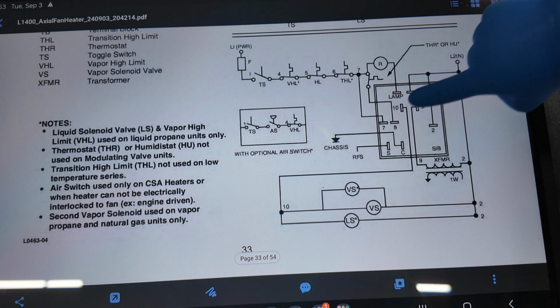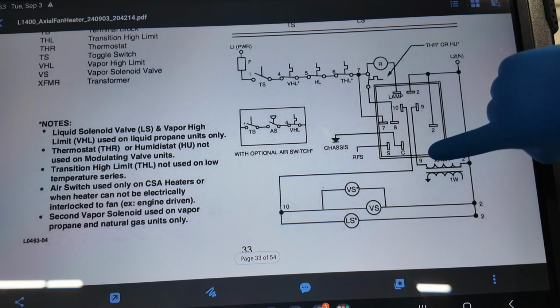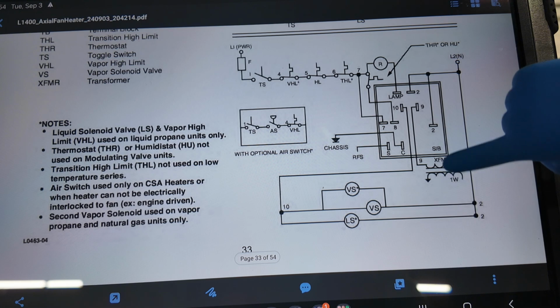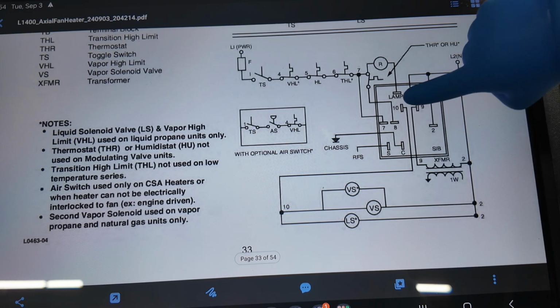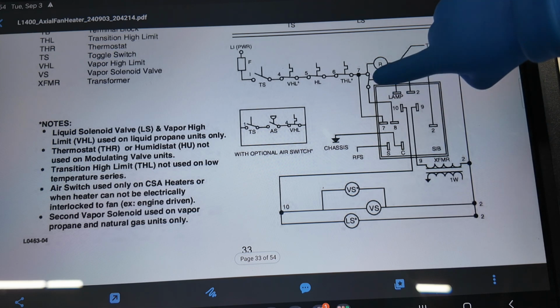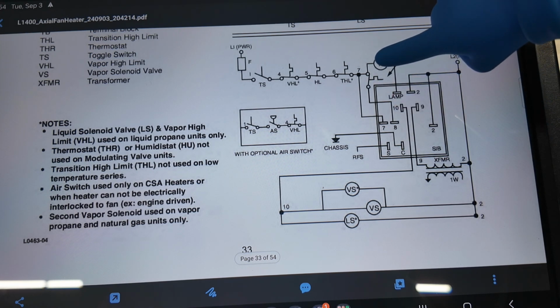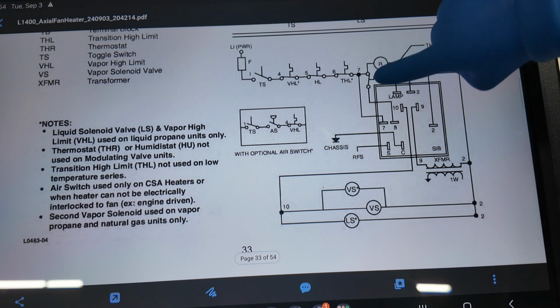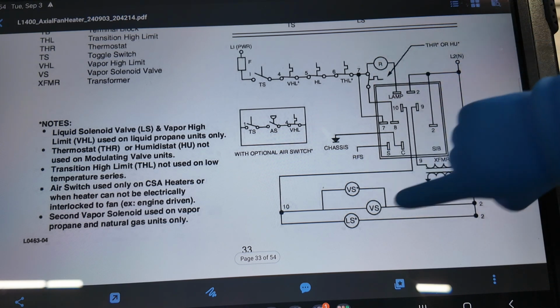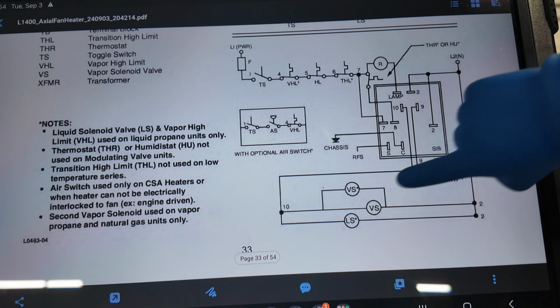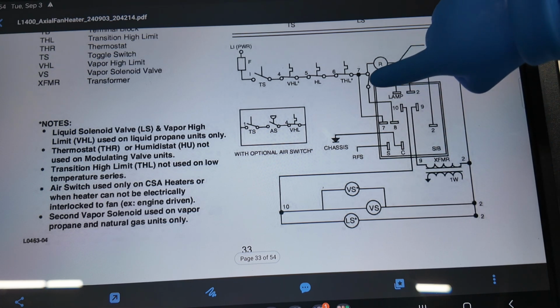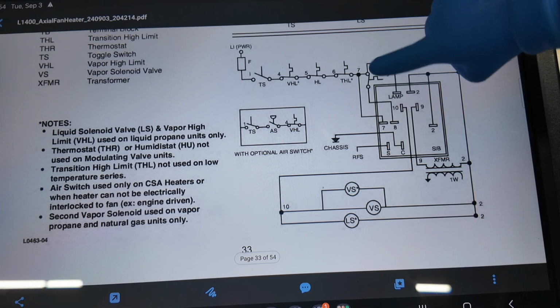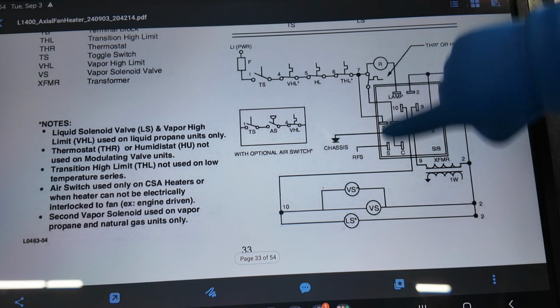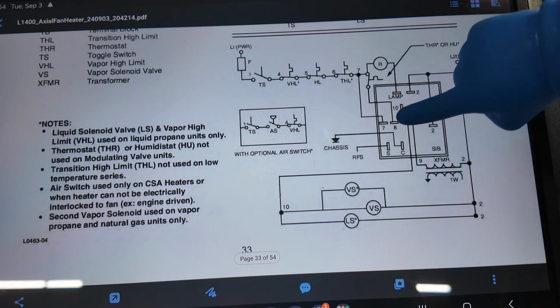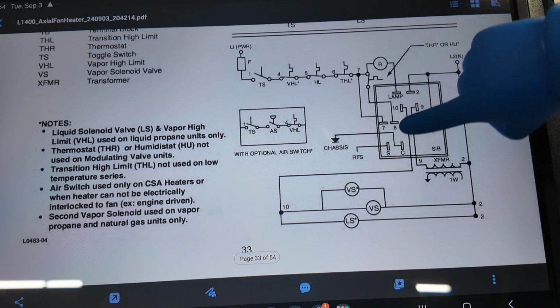You will get power on 9 and 10. 9 will have power for a short time to power your ignition transformer during ignition, and then it will turn off, and 10 will stay on to keep your burner running. If you disconnect 8, your lamp will stay lit and your burner will turn off. Gas valves and ignition will turn off, but your light will stay lit if you disconnect terminal 8. If you reconnect terminal 8 to 7, it will instantly turn the gas valves on. There's no purge time. That is your thermostat signal that goes to terminal 8.